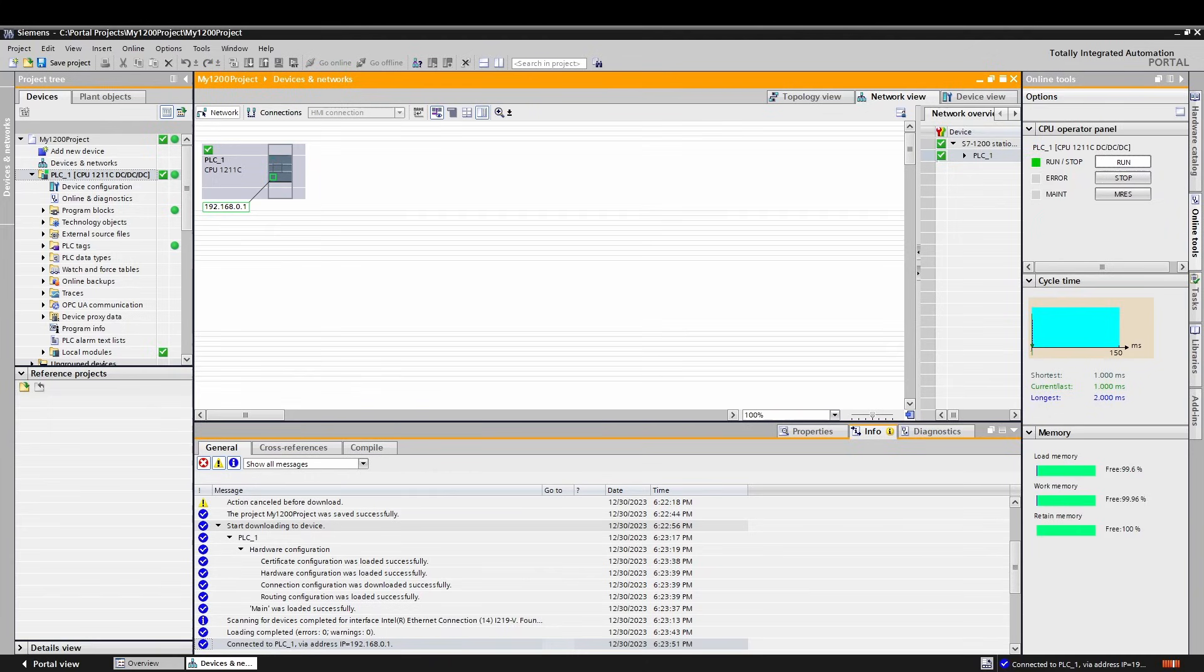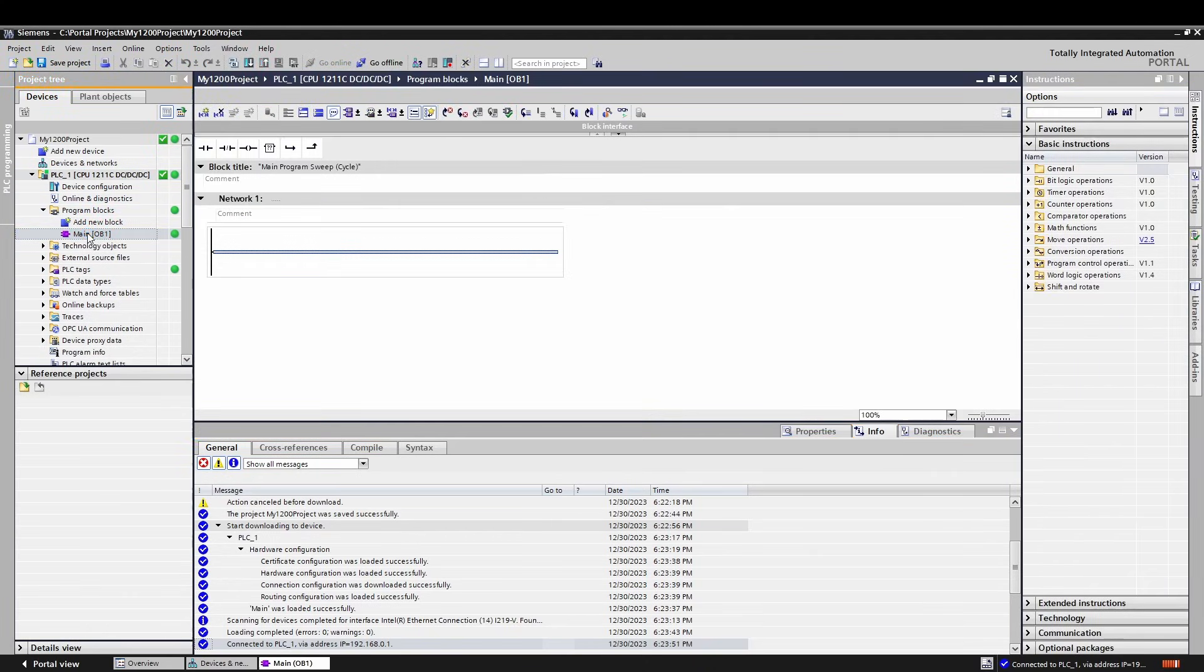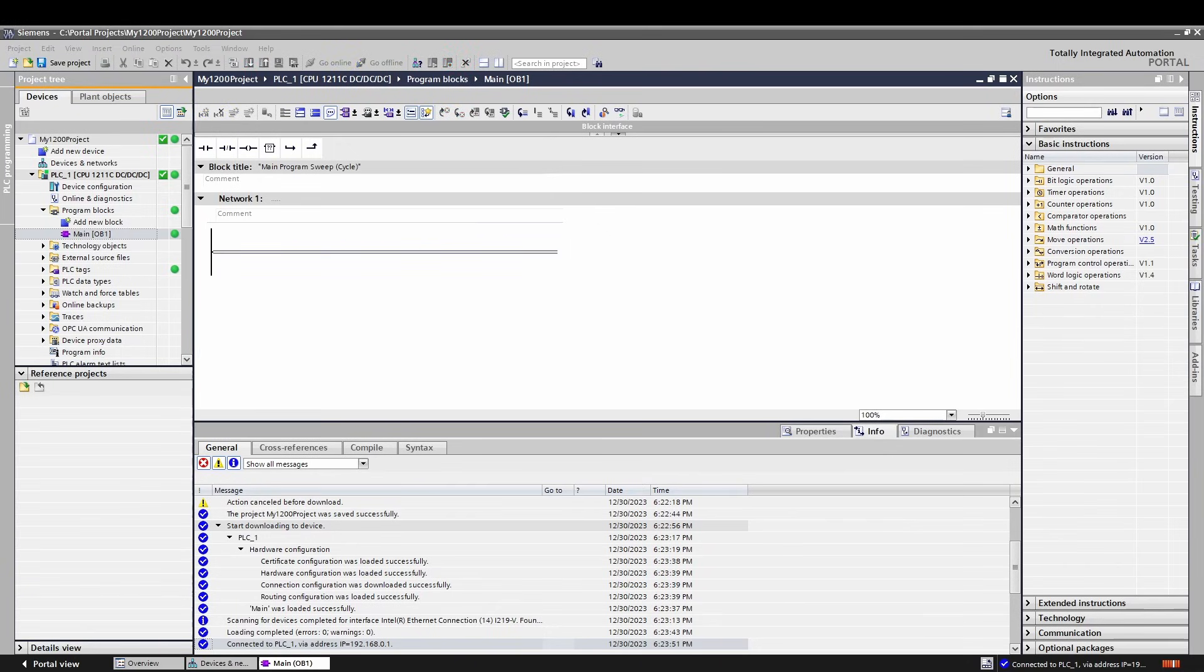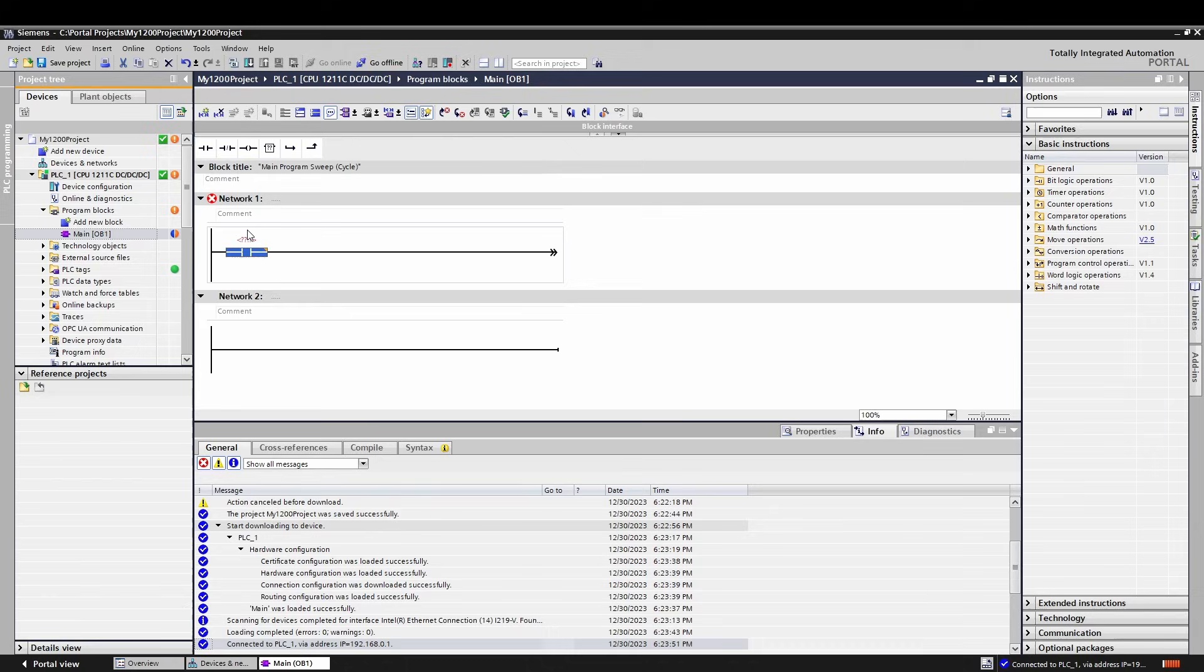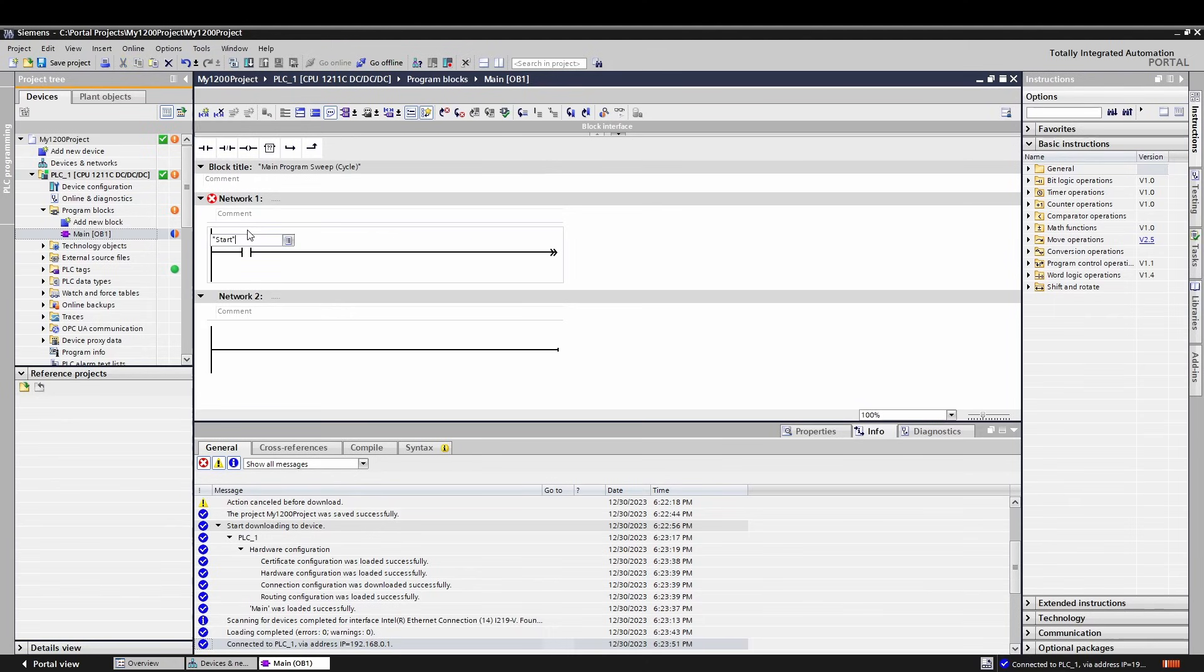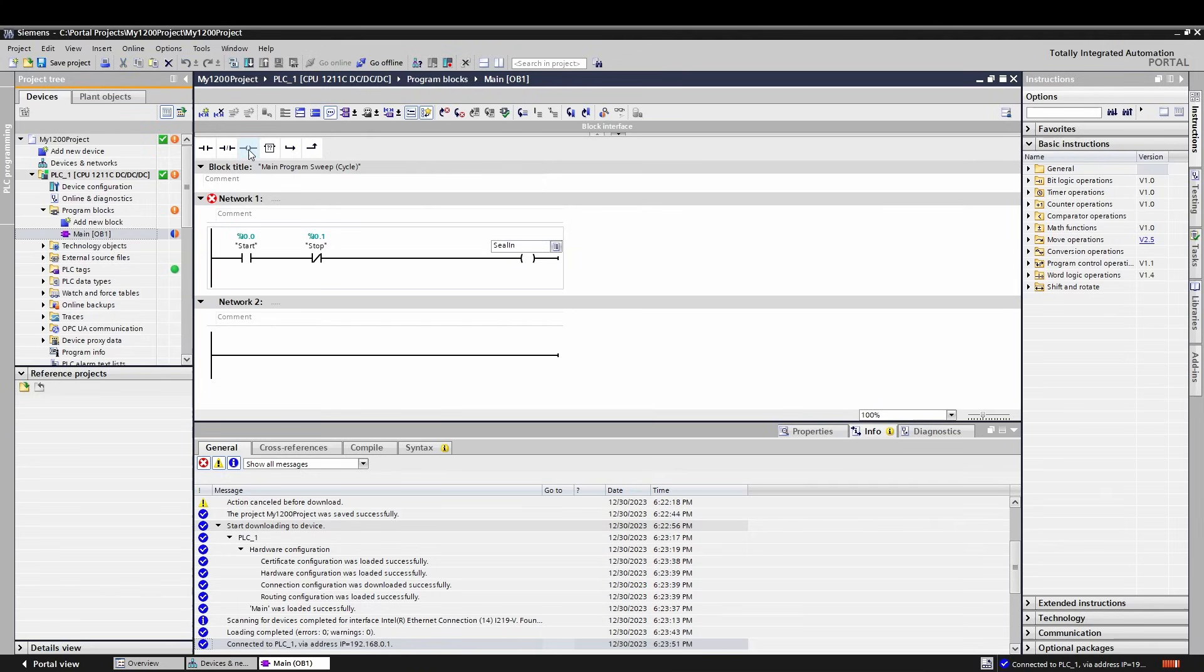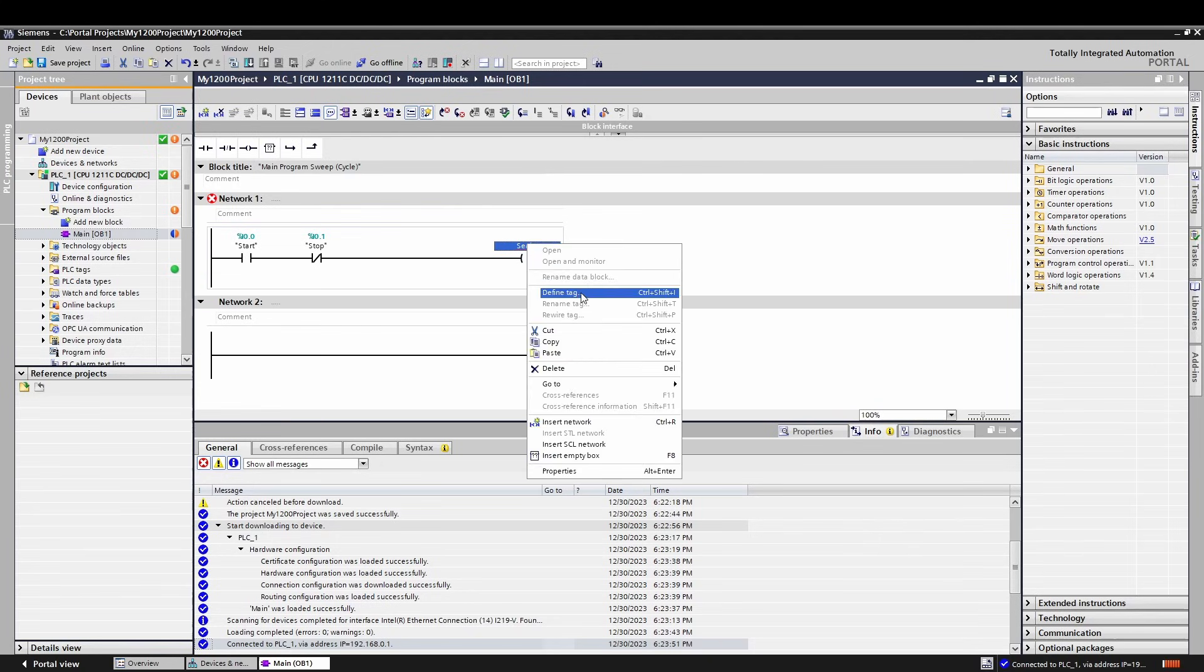Let's write a simple program that will get you started programming. For this introduction, we are going to write a single-line program to pulse an output on and off. We will write this program in OB1, so let's go ahead and open it. To learn more differences between OBs, FBs, and FCs, check out my full video on it, but for now just know that every program has an OB1 and it executes as fast as possible based on the performance of your CPU. This program will be written in ladder logic and will use two inputs, one output, one in memory, and two IEC timers. Let's bring in our two inputs. If you press the start button and the stop button is not on, it will turn on an internal bit.